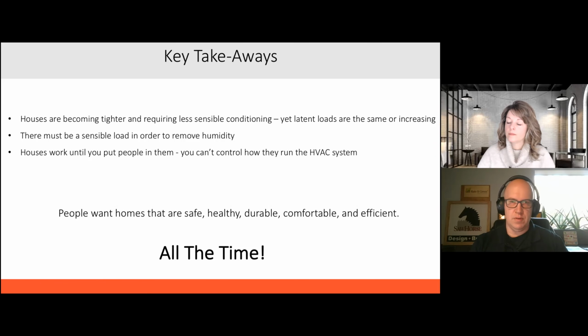But when you're retrofitting, most people are trying to retrofit products. And you mentioned the standalone dehumidifier is not going to work for what you need in most circumstances. You're not bringing that fresh air in. But what if somebody has a new HVAC system, so it's a high efficiency, at least 90% efficient plus, or it's all electric, but they still have that old water heater, and that water heater is atmospherically vented? So if we have a negative pressure in the house and the building envelope is tight-ish, we can have a condition where we're backdrafting.